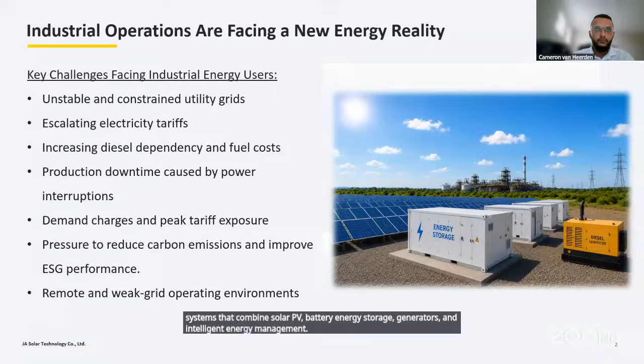So specifically, what is a hybrid energy system? At its core, it integrates multiple energy sources into one intelligent operating platform. Typically these systems combine solar PV generation, battery energy storage, utility grid supply, generators, and an EMS, or energy management system. The EMS acts as the intelligence layer, constantly monitoring energy demand, solar generation, battery state of charge, grid conditions, and generator availability. Based on this information, the system dynamically optimizes energy flow in real time.